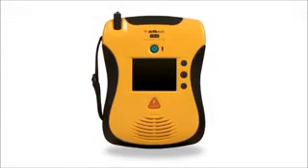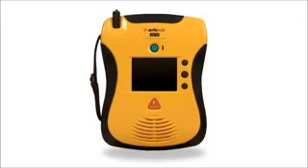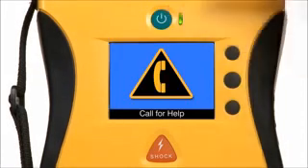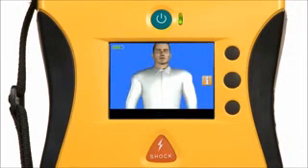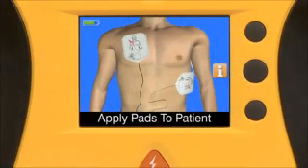Take a look. The first thing you'll notice about the new view is the video screen that shows you what to do in an emergency. Just one touch turns on the device, lights up the interactive screen, and a clear, calm voice tells you what to do. Remove clothing from patient's chest. The video screen shows you what to do with clear, easy to understand pictures and texts, so you can read it, see it, hear it.